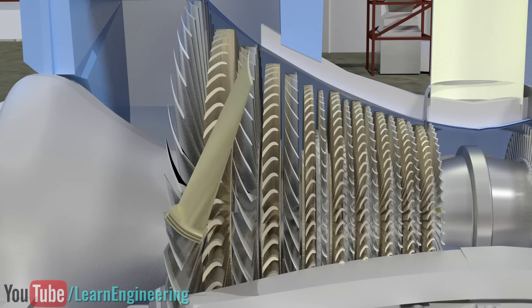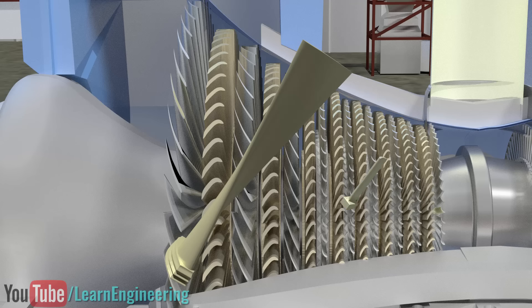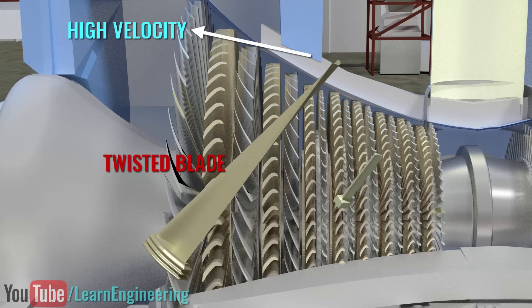You can see how long the last stage turbine blades are compared to the first stage blades. The tips of such long blades will have very high velocity compared to the root. A twist is given to it so that all blade cross-sections will remain at an optimum angle of attack.